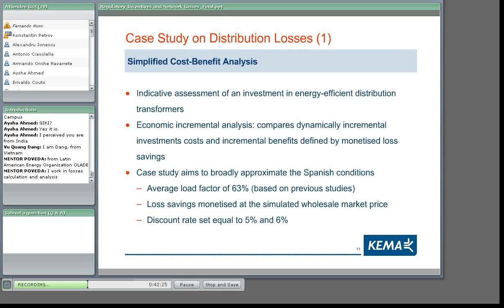To put this analysis in context, we selected two types of transformer, with support from the European Copper Institute — you can see this in the report as table 1. We used two types of transformers, 400 kilovolt-ampere and 630 kilovolt-ampere, with specific parameters as indicated in the report. We tried to measure the effect on these two transformers using one conventional and one efficient transformer, meaning with loss reduction functions.